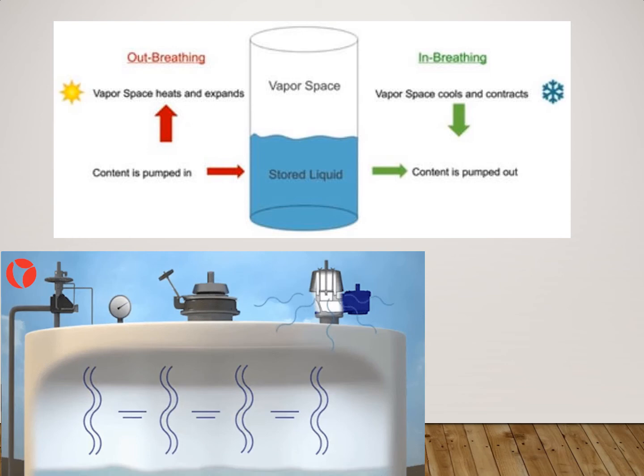Liquid is stored in the storage tank with vapor space above it. As the sun rises in the morning, the vapor space inside the storage tank naturally gets heated up, causing the pressure inside the tank to build. The pressure side of the breather vent begins to open, relieving the pressure to a safe level. As the liquid level begins to fill the tank, pressure will increase, and the pressure side of the vent opens to relieve it.